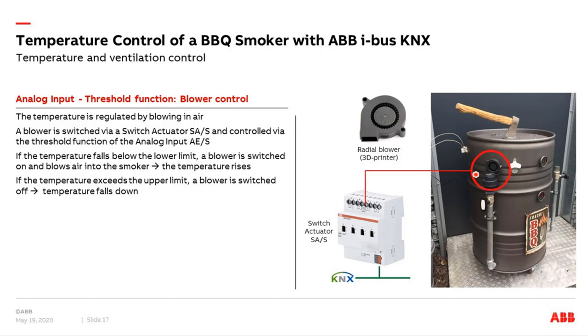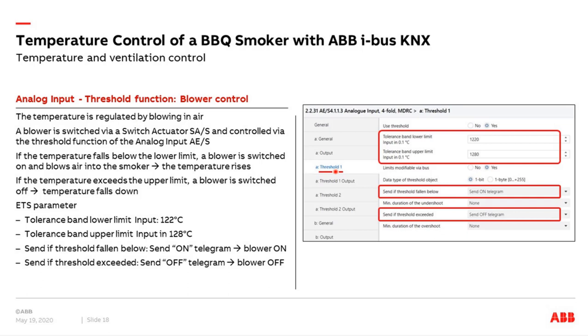In the settings, we enable threshold number 1. We set our temperature value — for example, the lower limit at 122 degrees and the upper limit at 128 degrees. We want to modify the values via bus, so we say yes. Then we set the behavior: when the temperature falls below 122 degrees, switch on the blower; when the value exceeds the upper level, switch off. These are the typical settings for threshold function number 1.